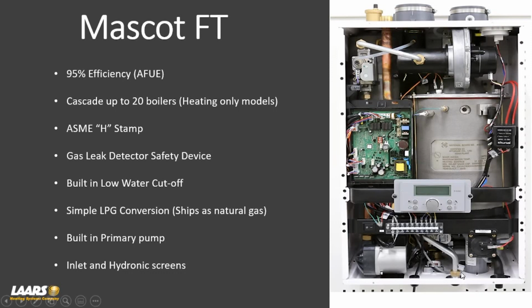Now also, while we're here, I want to talk about a condensate trap. We have a built-in condensate trap right in the cabinet. And that's a clear trap. And what I'm getting at is anybody doing any service or you go back to do maintenance on a product, that should be one of the first things service technicians are looking at. I don't care whose product it is.